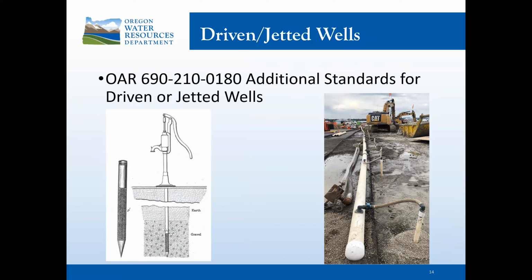Driven and jetted wells construction standards are stipulated in OAR 690-210-0180, and all drive point wells or jetted wells shall have non-perforated watertight casing meeting the minimum specifications shown in table 210-1 and extend a minimum distance of 18 feet below land surface.